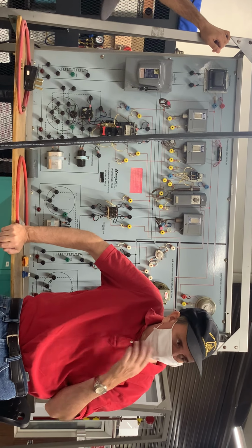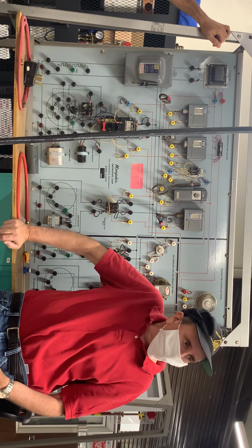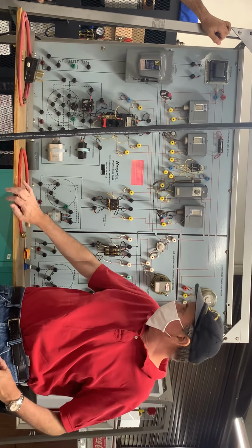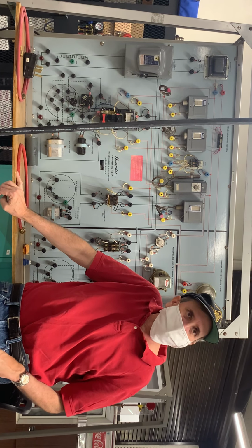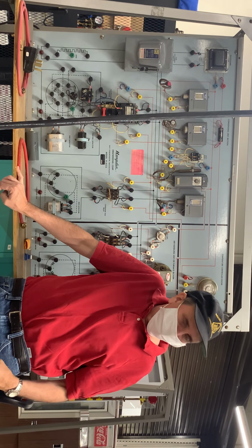So by the time it hits the compressor, you already lost a lot of voltage in the system, right? No, no. The wires are good wires, relatively short, under 50 feet. The connections are all good. So it didn't drop any? No, well, on this board there are some weird wires going inside doing some things, so you might find like one tenth or two tenths of a volt that I don't know what's happening to. But in the real world, no.